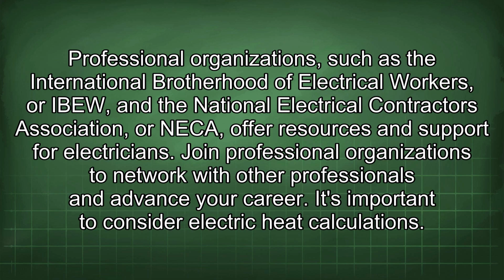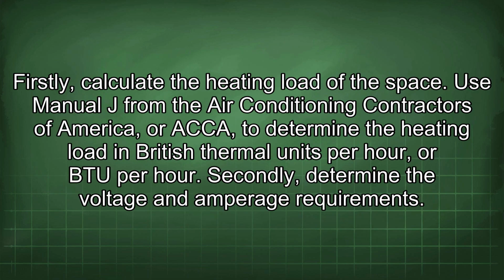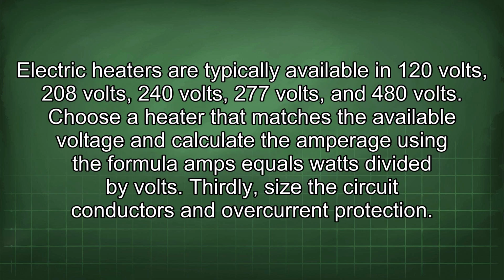It's important to consider electric heat calculations. Firstly, calculate the heating load of the space. Use Manual J from the Air Conditioning Contractors of America, or ACCA, to determine the heating load in British thermal units per hour, or BTU per hour. Secondly, determine the voltage and amperage requirements. Electric heaters are typically available in 120 volts, 208 volts, 240 volts, 277 volts, and 480 volts. Choose a heater that matches the available voltage and calculate the amperage using the formula amps equals watts divided by volts. Thirdly, size the circuit conductors and overcurrent protection.